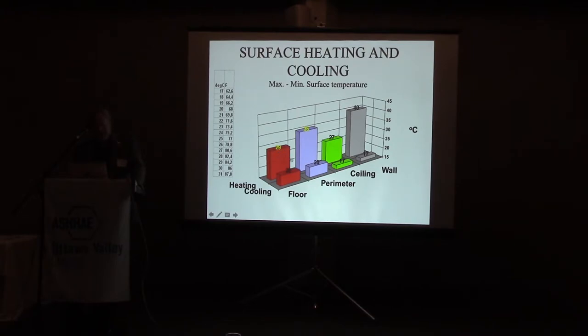For cooling, depending on if you're standing or sedentary, we could go down to 19, as we say in the ASHRAE standard. But I recommend not lower than 20 for a sedentary person. So when we have floor cooling, it's not like the floor is very cool, it only goes down to about 20 degrees. Now, in the standards, there are both ISO standards and European standards for these radiant heating and cooling systems. It is allowed in the perimeter, the first meter or half meter from the outside facade, to have a higher temperature on the floor, because it's really outside the occupied zone.